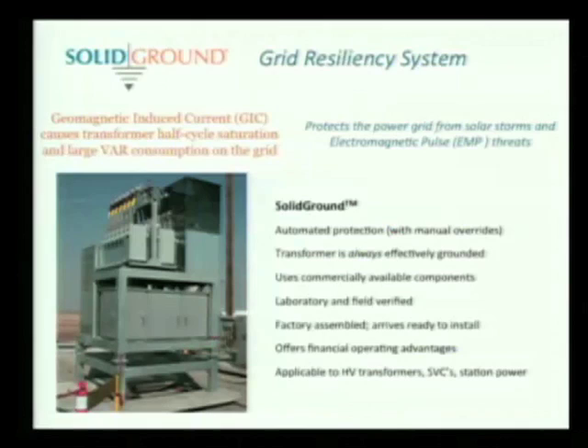So the Solid Ground system, and in a minute I'll describe how it works, its intent is to protect the power grid from solar storms and electromagnetic pulse. It's automated protection. The transformer is always effectively grounded. You'll see 3 paths to ground for the neutral, and when called upon, it blocks the neutral. It's a neutral blocking device. It uses all commercially available parts, so there's nothing special in any part of this that we build. It's all off the shelf. So we just put a system together.